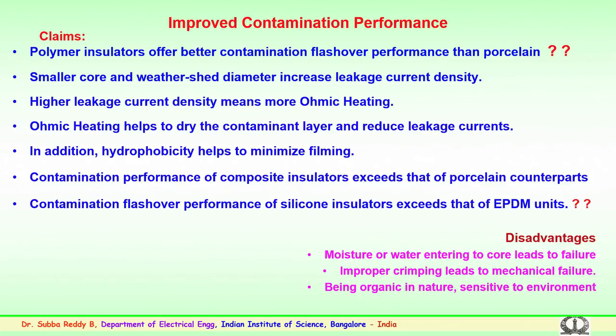This phenomenon is very important because, as we discussed, pollution or contamination is a very serious threat above extra high voltage, that is 400 kilovolts and above. Contamination plays a major role in the line design of EHV systems. So, the better performance of composite insulators during contamination or pollution is a major advantage in comparison to other types of insulating materials.